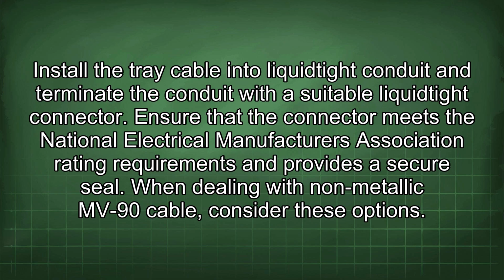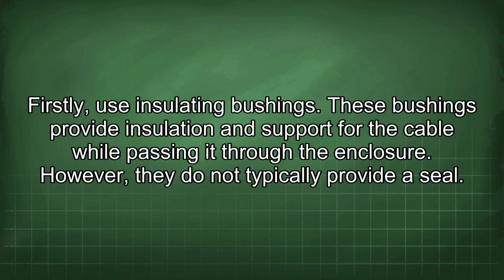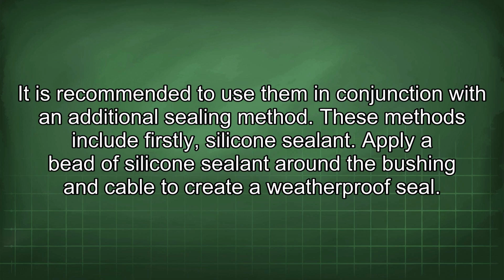When dealing with non-metallic MV-90 cable, consider these options. Firstly, use insulating bushings. These bushings provide insulation and support for the cable while passing it through the enclosure. However, they do not typically provide a seal. It is recommended to use them in conjunction with an additional sealing method.